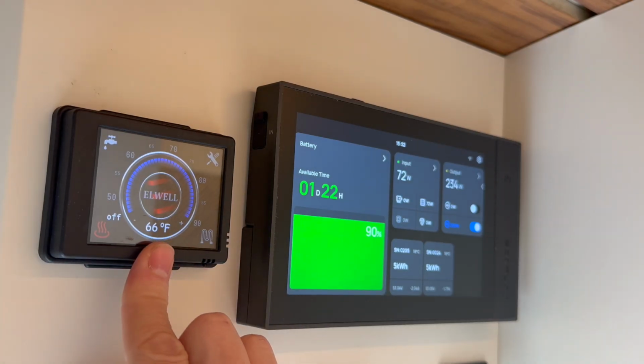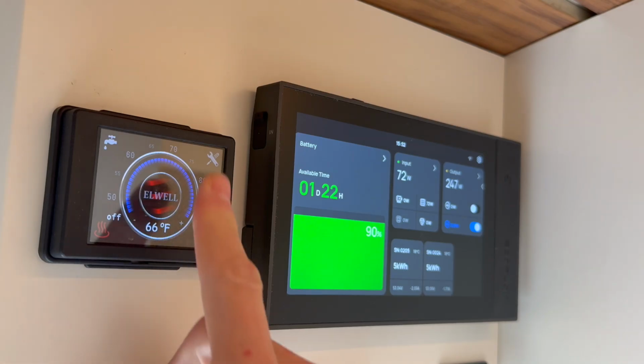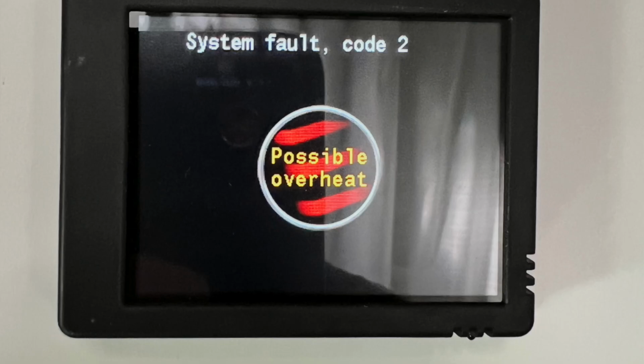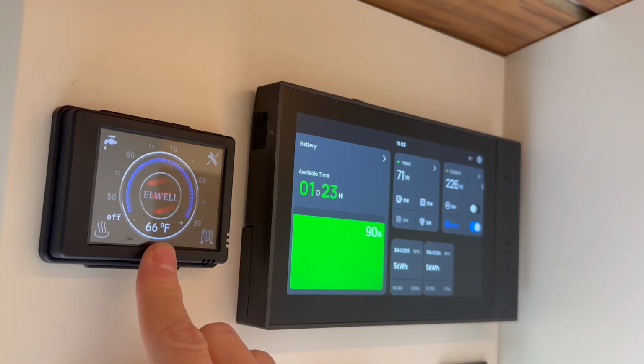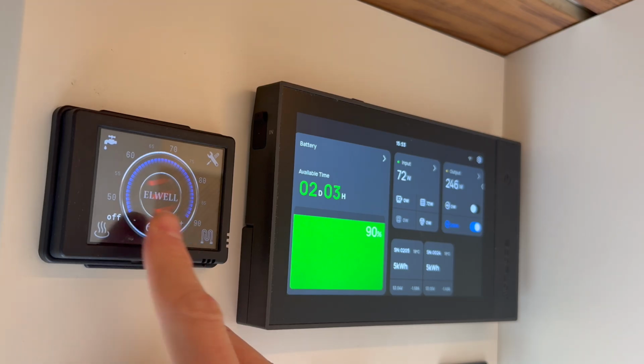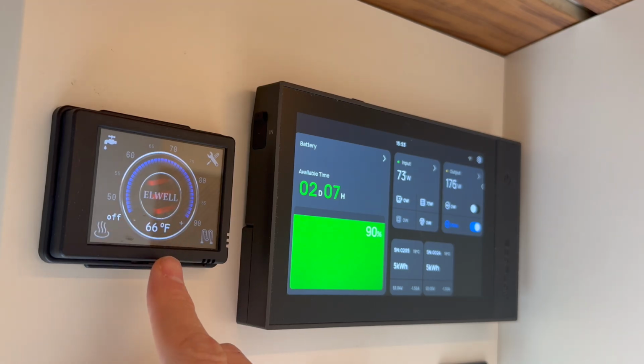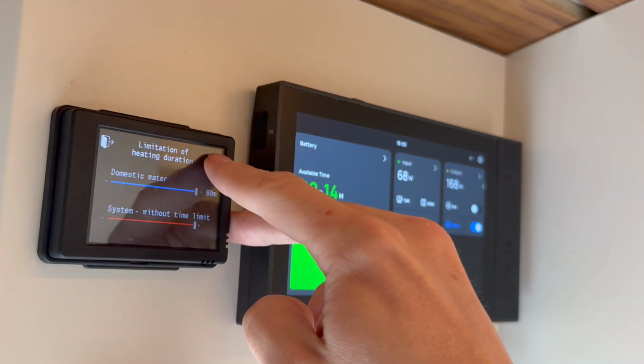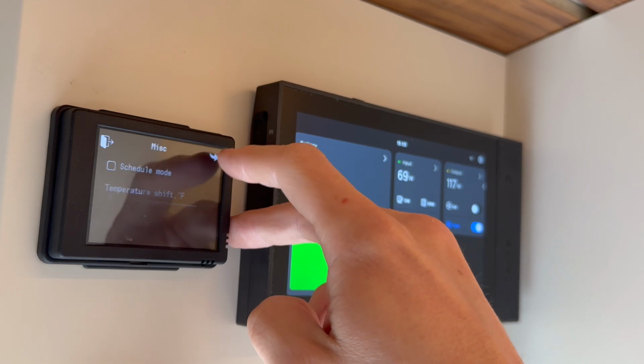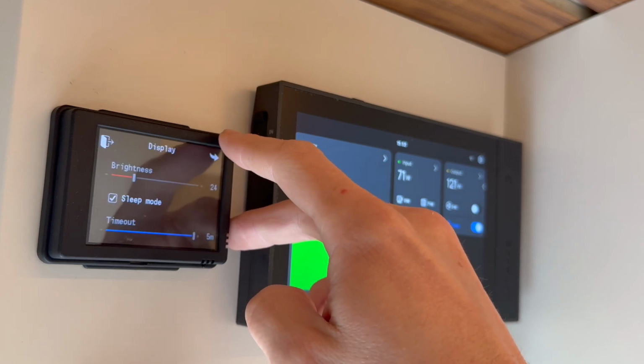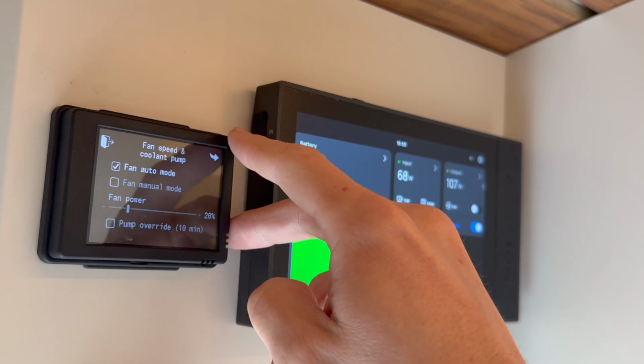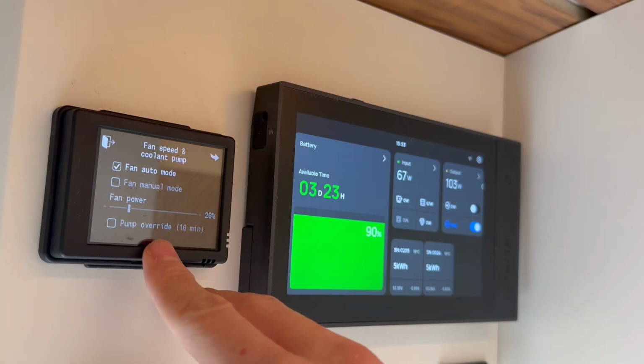Another common problem that you might have is overheating. If you get the overheating error code, it will turn off the heater. Overheating 90% of the time means that there is a bubble in the line somewhere. One of the main ways to fix that problem, in the settings, go to the page that gives you the option to override the pump here.